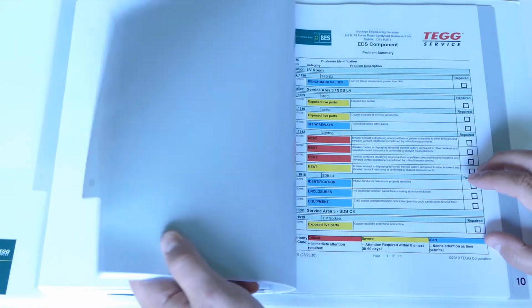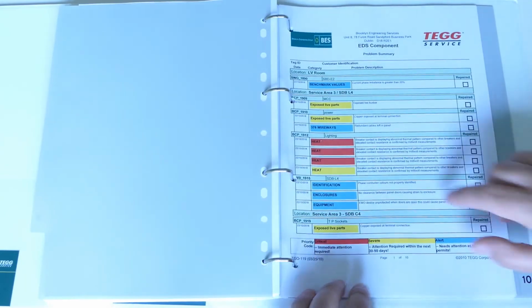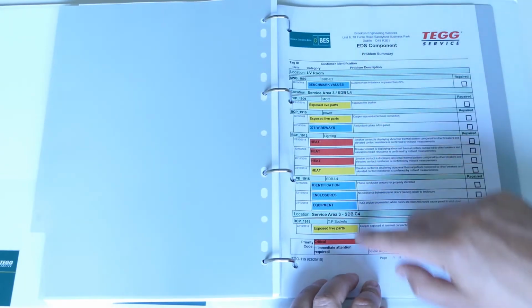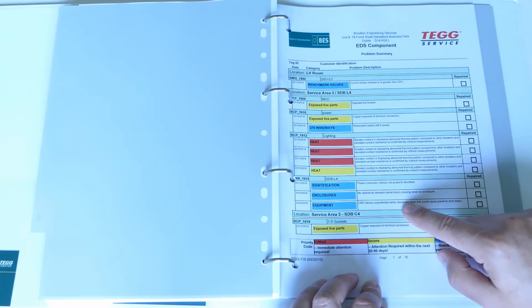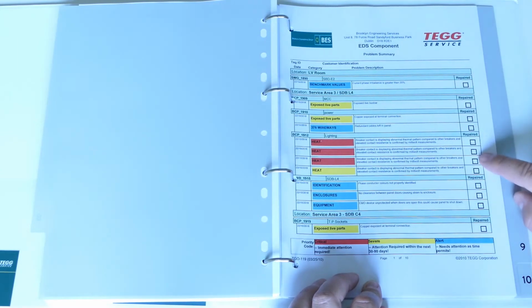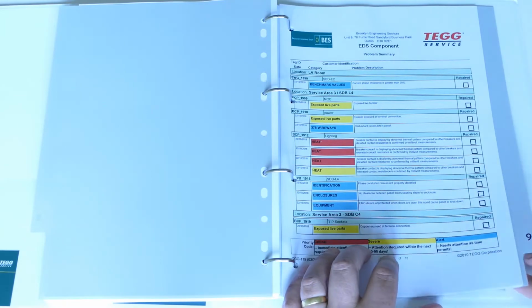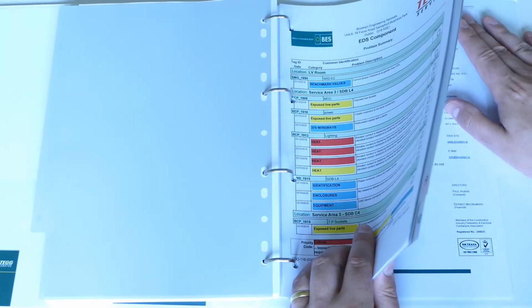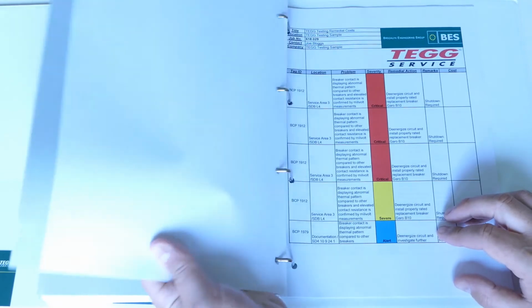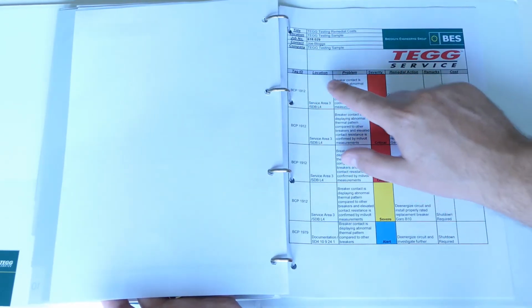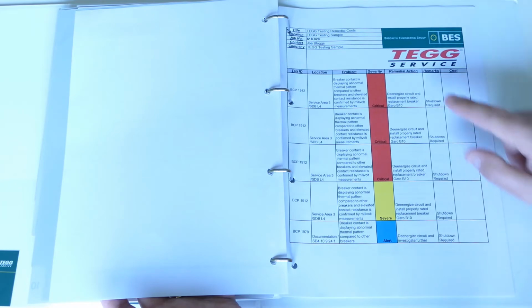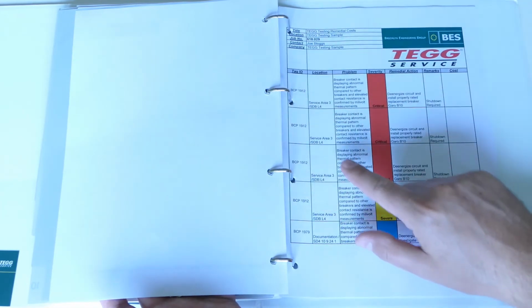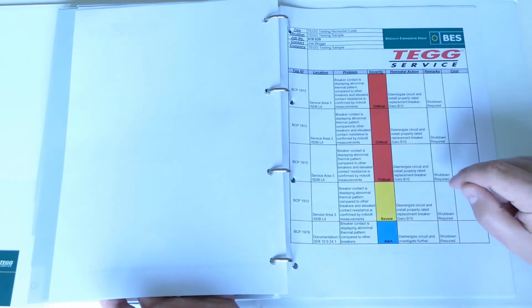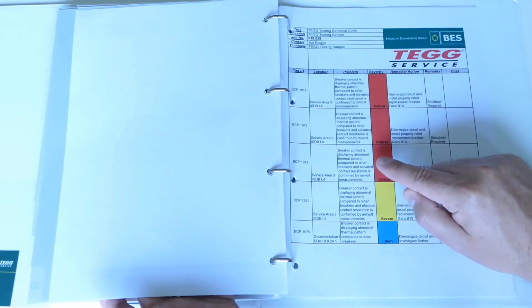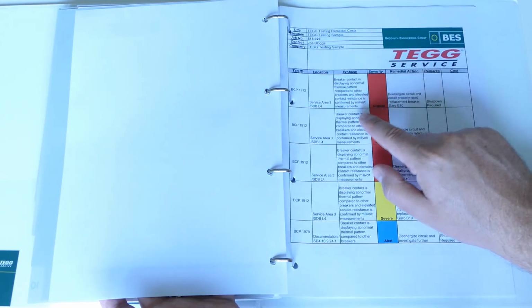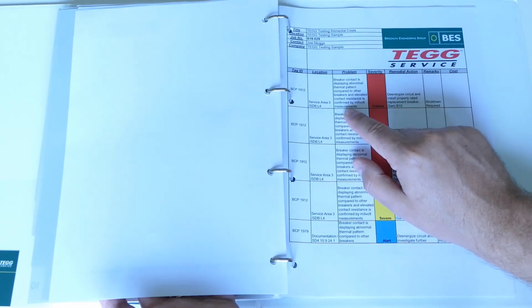Section number 8 then is our problem summary. Again, you'll see the colour-coded breakdown of how severe the issues are, detail of the issue, and if it was repaired on site, this box will be ticked to indicate that. Section number 10 corresponds with this section, so you can see here you have your tag ID, location, problem, severity, remedial action and remarks. So for example, branch panel 1912 in service area 3, the breaker contact is displaying an abnormal thermal pattern compared to other breakers, and elevated contact resistance is confirmed by millivolt drop measurements.